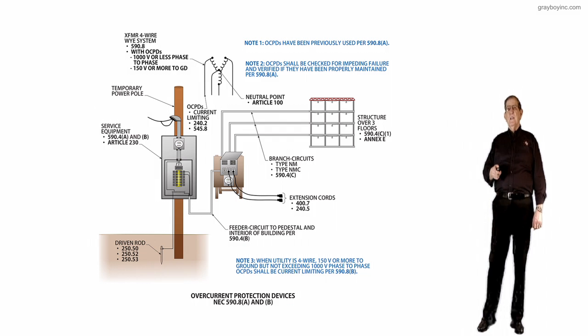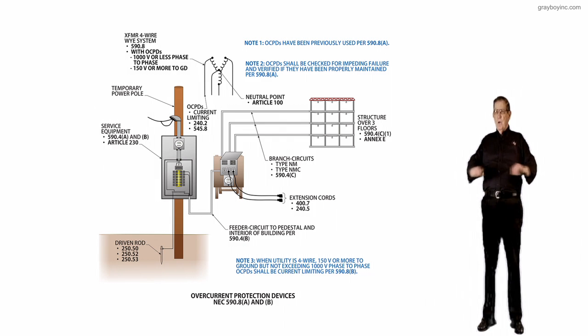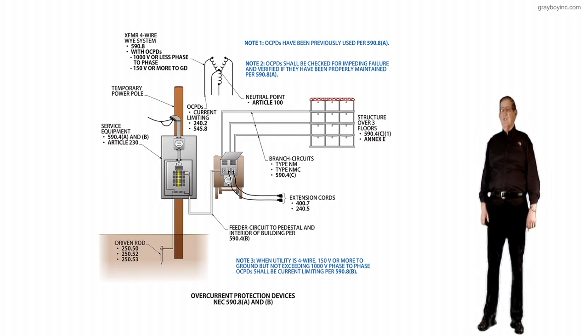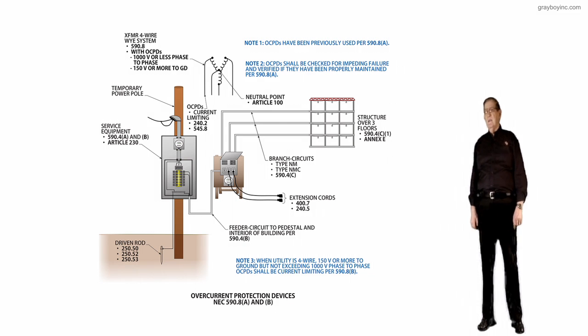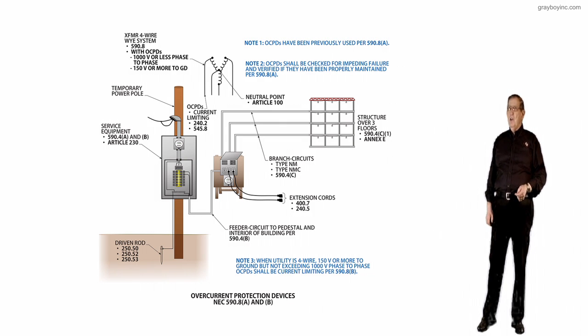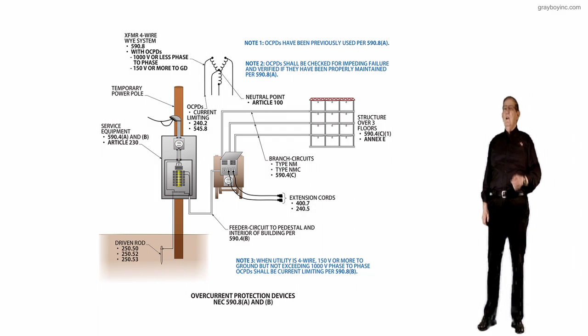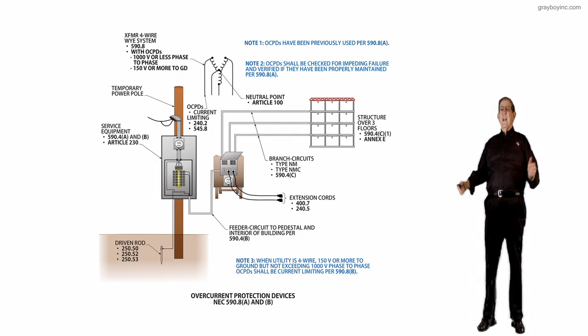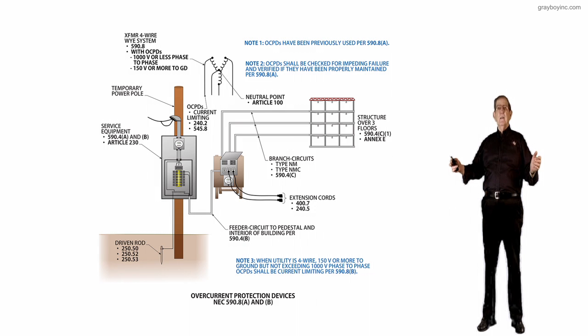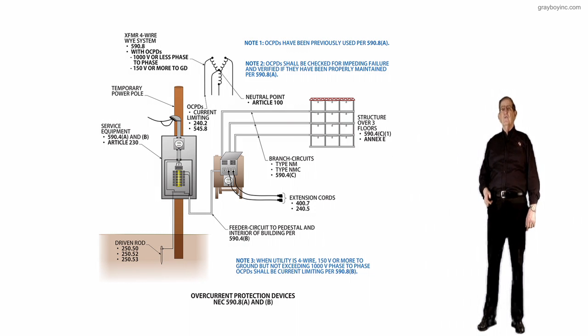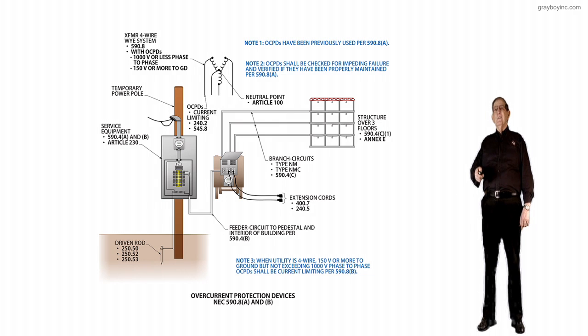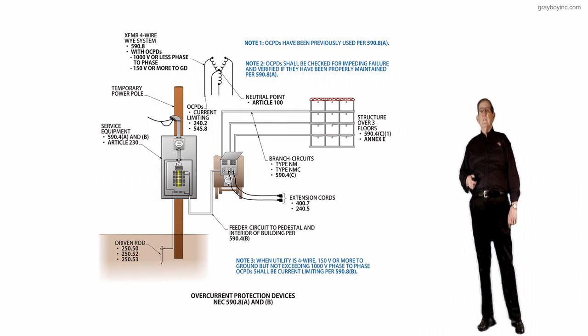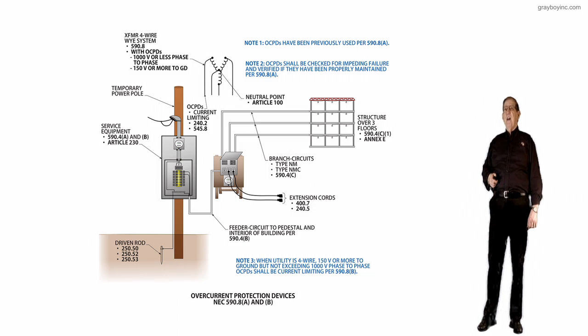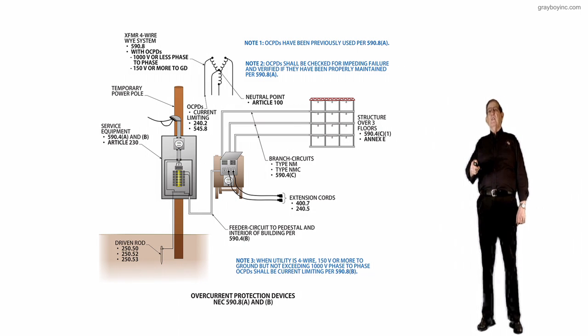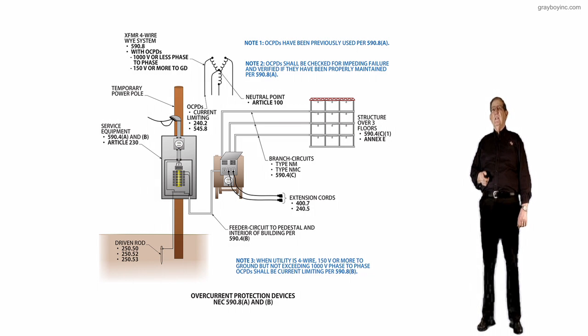And we know that we could have a cord run on the ground, above ground, and we could couple it together up to 100 foot with a sleeve. We know that would be permitted. And I believe it's 400.14 or 17 where this is permitted as a sleeve. But it's got to be above ground, not in the ground. So those are some of the things you might want to look at. And then cord and plug connected cords is 400.7 and 240.5.